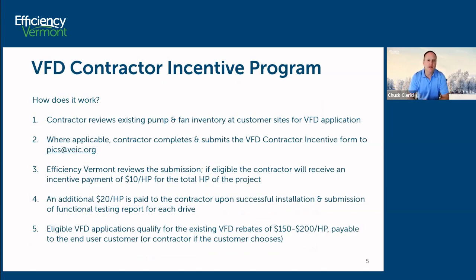So how does the program work? Contractors review existing pump and fan inventory at customer sites for VFD application. There'll be a table and another slide or two that points to the 7 end-use applications that cover probably 95% or greater of the pump and fan loads in HVAC. Where applicable, the contractor completes and submits the VFD contractor incentive form and sends it to pics@veic.org. That kicks off an internal process that sets up an opportunity in our system.